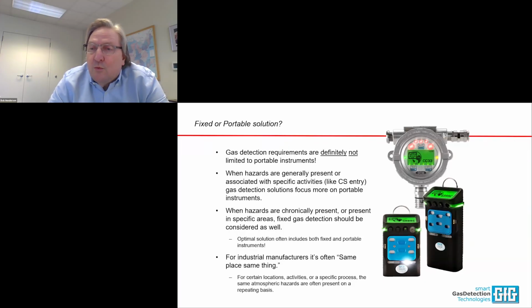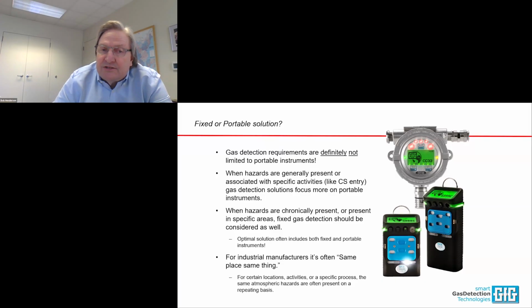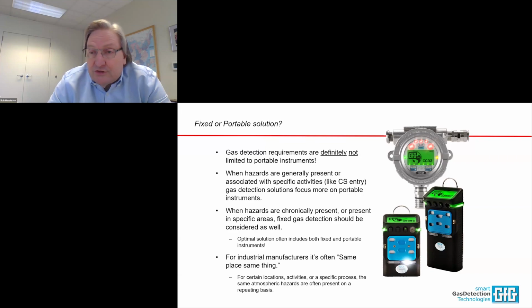It's a nice formulaic way to make sure you haven't missed something along the route to a conclusion as to what you need. Gas detection requirements, again, are not limited to portable instruments. When the hazards are generally present or associated with specific activities, like confined space entry, often gas detection solutions are going to focus more on portable instruments. So if you have H2S anywhere on site, someone entering the site is going to have a personal H2S monitor at a dead minimum. You can't get in the front gate in that case without it.